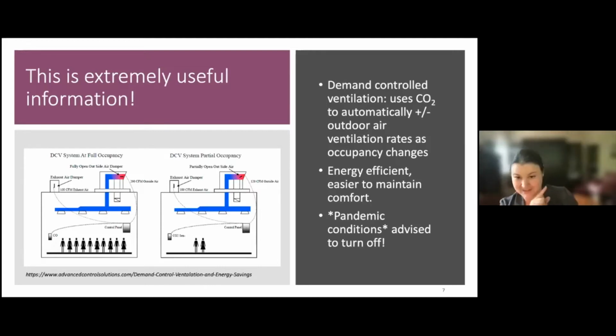During the pandemic, facilities were advised to turn off or disable their demand control ventilation systems, or set the set point to 400 ppm, to be sure fresh air intakes weren't shut off when CO2 was low. Think of a long-term care home where people are sedentary and not producing much CO2, but there are still a lot of people there—you would not want the fresh air intake turned off. That could be very dangerous in a pandemic situation.